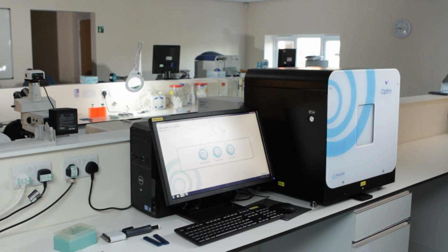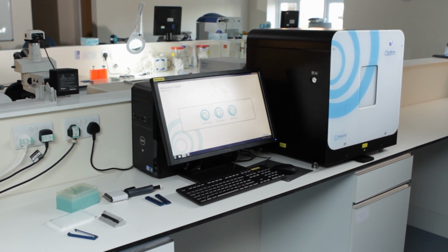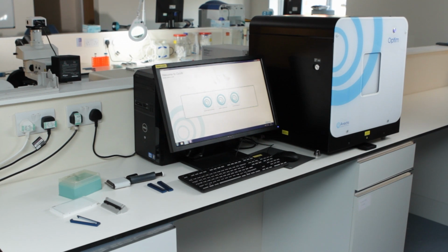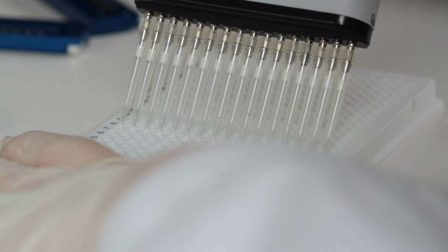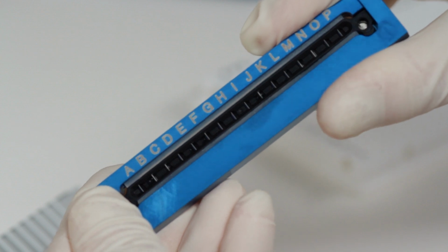The Avacta Optim is a step forward in the development of biotherapeutics, simultaneously providing information about aggregation state, conformation and other stability indicating parameters, with parallel measurements of up to 48 samples in just a few hours.